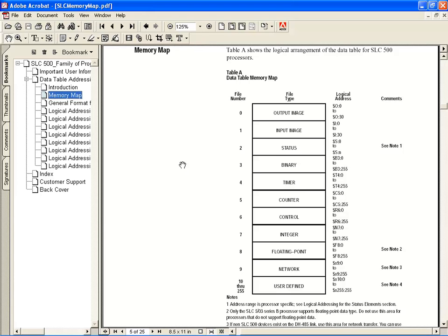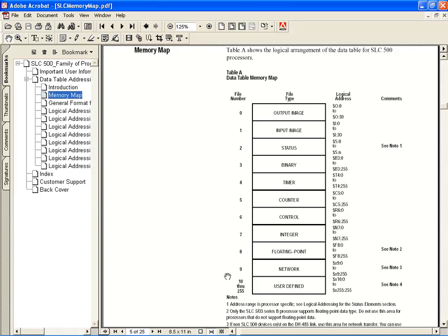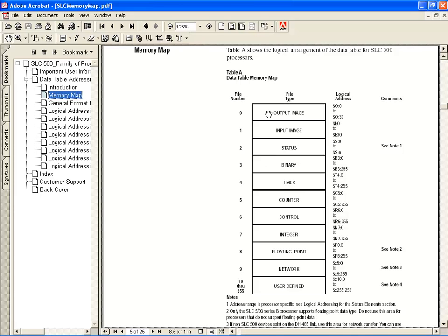I've taken this screen from one of the SLC downloadable PDFs from Allen Bradley's website. Here we have the memory map of the SLC processor, a lot more straightforward than the previous example. Here we have our file number. The standard file setup is 0 through 8 or 9 depending on the PLC type, and then user defined is 10 through 255. We can have 0 to 255 data files, of course limited by the amount of memory in the PLC. File number 0 is set aside for output images and so on. You'll recognize 0, 1, 2, 3, 4, these various data files in your program. Let's go and have a look at the software now.